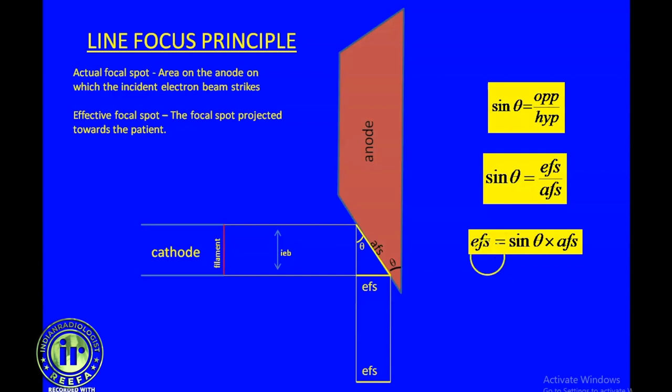In diagnostic radiology, the anode angles usually range from 10 to 13 degrees, and the size of the effective focal spot ranges from 0.6 to 1.3 millimeter. For procedures like cineangiography, the anode angle is further reduced to around 7 to 9 degrees.